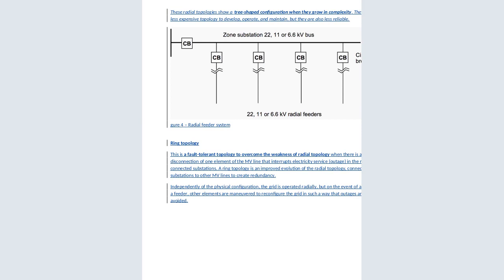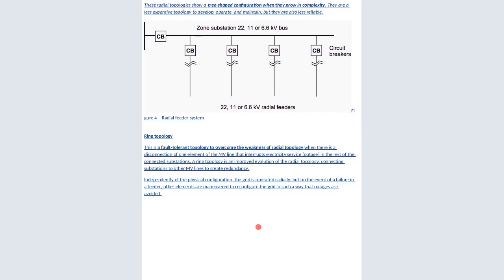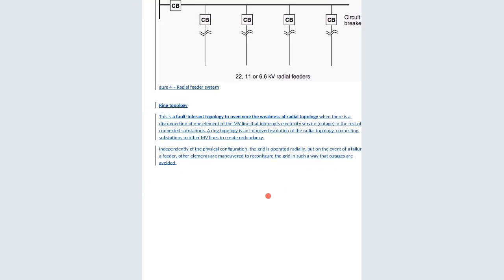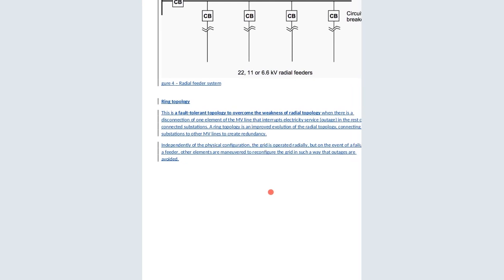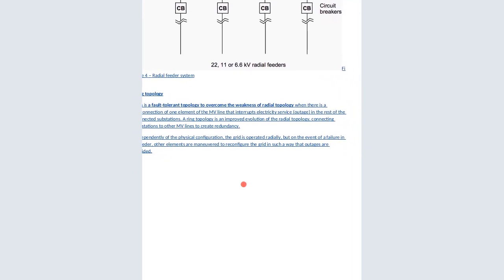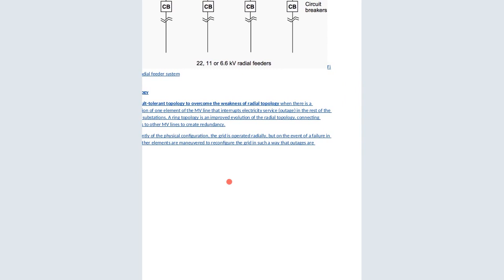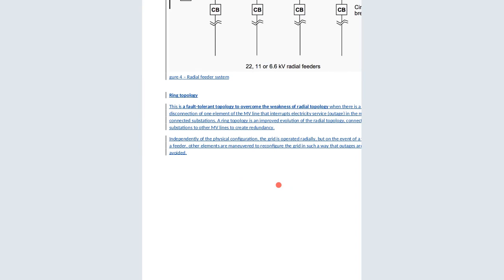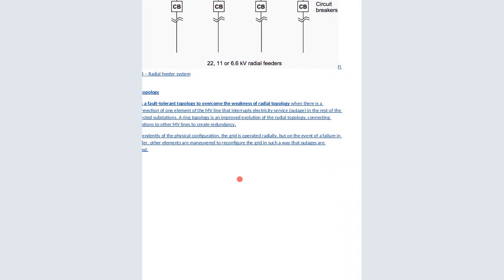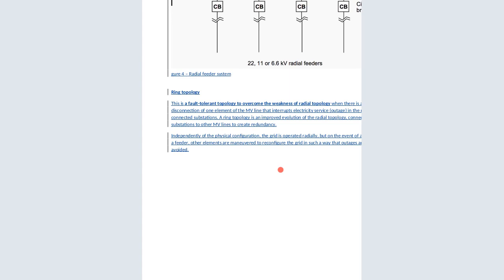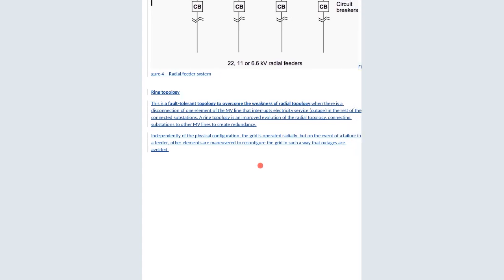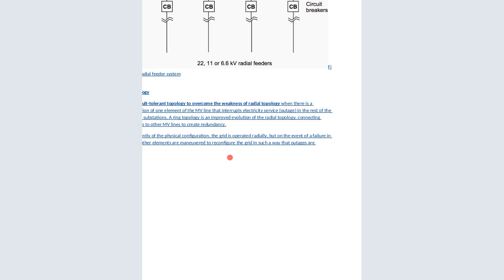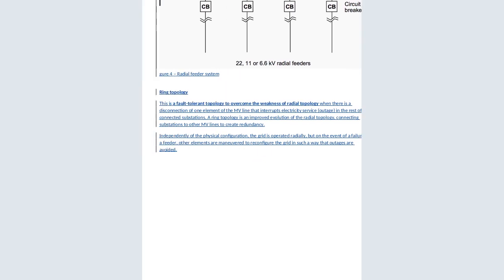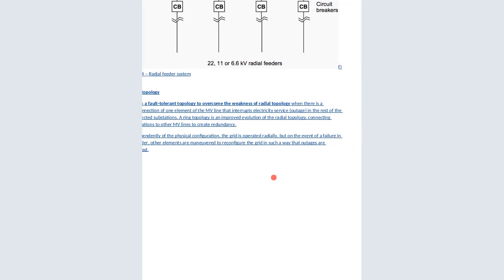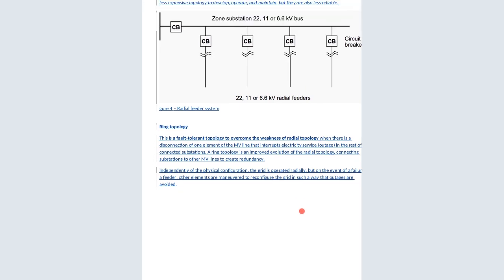What about the ring topology? The ring topology is a fault tolerant topology to overcome the weakness of the radial topology. When there is a disconnection of one element of the MV line, that interrupts electricity service, causing an outage in the rest of the connected substations. So a ring topology is an improved evolution of the radial topology, connecting substations to other MV lines to create redundancy. Independent of the physical configuration, the grid is operated radially, but in the event of failure in a feeder, other elements are maneuvered to configure the grid in such a way that outages are avoided. So ring topology is one of the solutions.